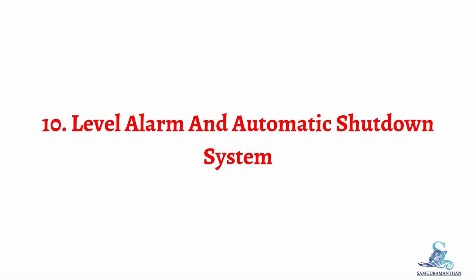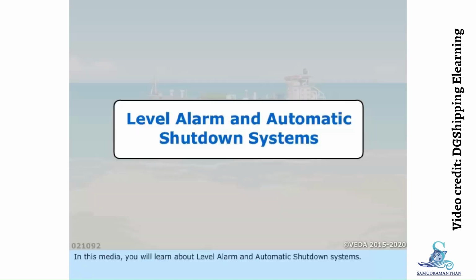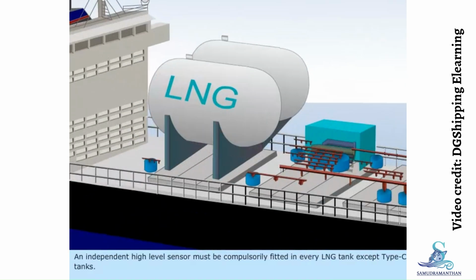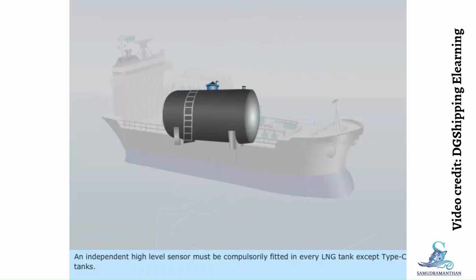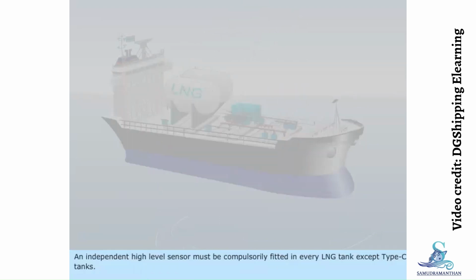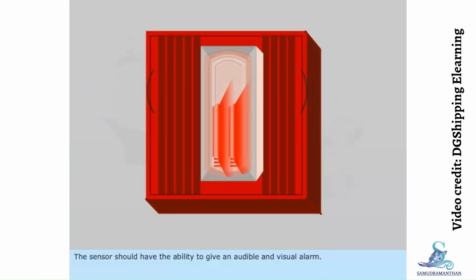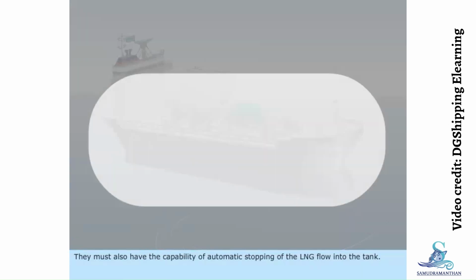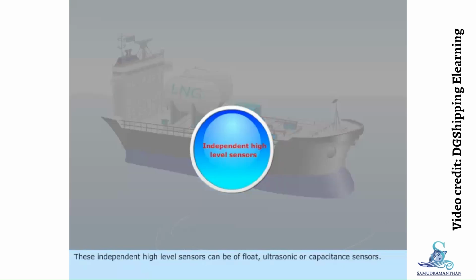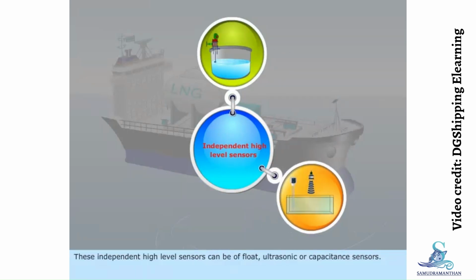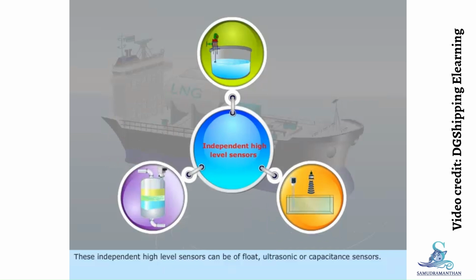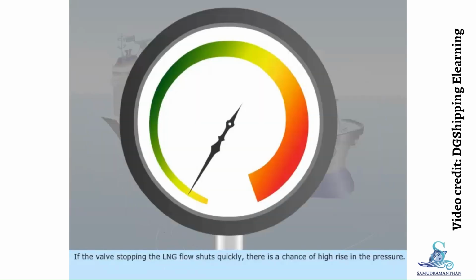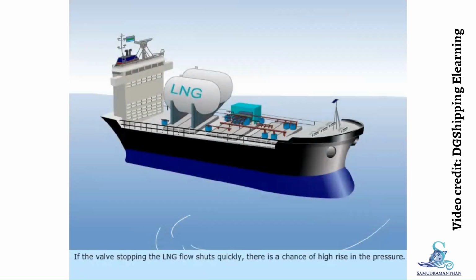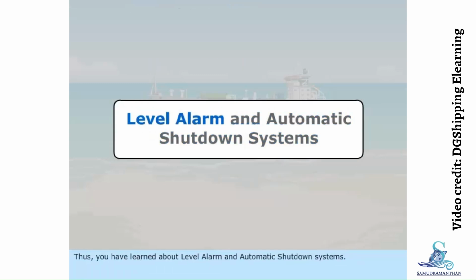Topic 10: Level Alarm and Automatic Shutdown System. In this media, you will learn about level alarm and automatic shutdown systems. An independent high-level sensor must be compulsorily fitted in every LNG tank except Type C tanks. The sensor should have the ability to give an audible and visual alarm. They must also have the capability of automatic stopping of the LNG flow into the tank. These independent high-level sensors can be of float, ultrasonic, or capacitance sensors. If the valve stopping the LNG flow shuts quickly, there is a chance of high rise in the pressure. Thus, you have learned about level alarm and automatic shutdown systems.